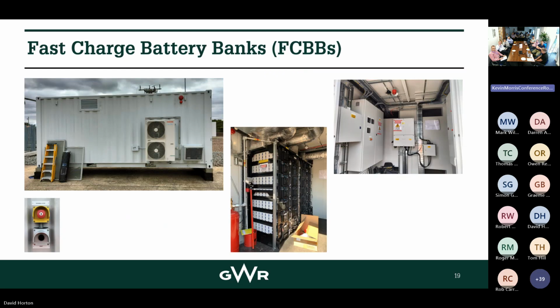This is just a picture of the fast charge battery banks. As I say, it's a 20-foot container with an aircon unit on the side of it. Same principle applies as on the train. We're trying to keep the batteries inside in a stable environment. Half the container is devoted to the batteries in racks, and the other half has got the switchgear in it. On the outside is an emergency stop button.